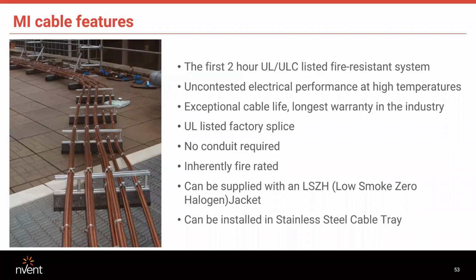It's a good photo. The cable is required to be supported every 6 feet horizontally, 6 feet vertically, and you bundle them together, ABC, neutral if there's a neutral. So you bundle them together like that. And the reason why you bundle them together is so you get the sheath currents, which will rotate around the cable, to cancel each other out. If you don't bundle them together, the sheath currents could create an induced voltage, which could manifest itself as voltage drop along the run of the cable.